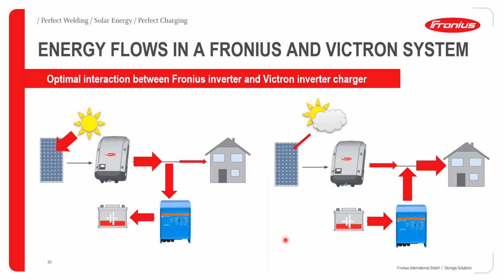So in terms of the power flow in such a system, just to give you this information, during the day, as I have mentioned, you could have a situation whereby the panels are generating maximum power, and therefore you have some of that going to the loads for consumption, and then any surplus available is regulated by the Victron inverter charger by using frequency shifting to be able to recharge the batteries accordingly. On the other hand, you could have a situation whereby there is a bit of irradiation deficiency, or there's dust cover, or there's cloud cover, and then the Fronius inverter is not able to give you as much power as is required by the load at this particular moment.